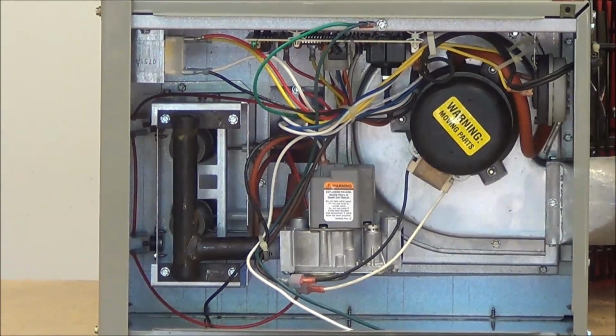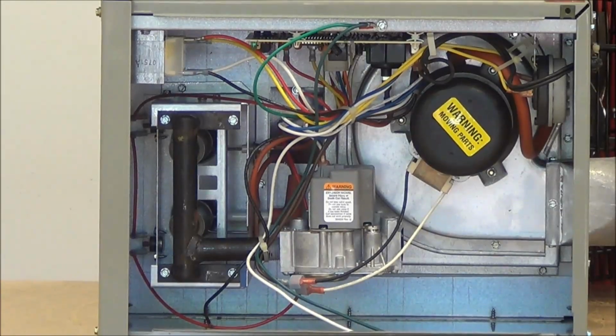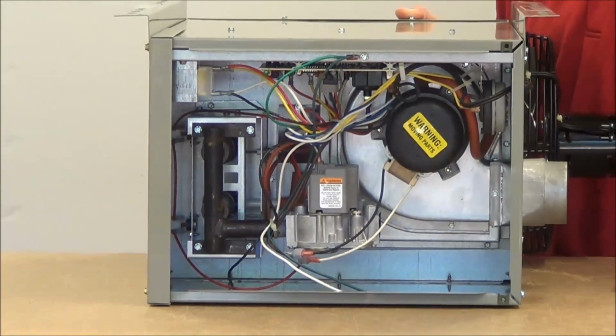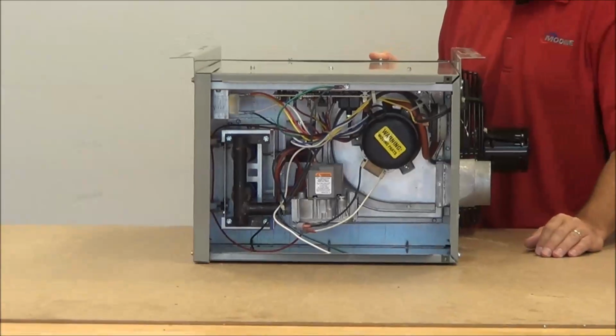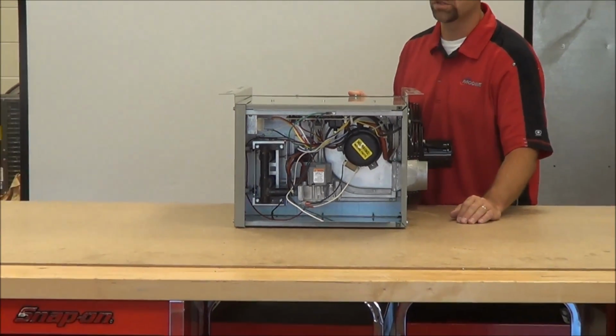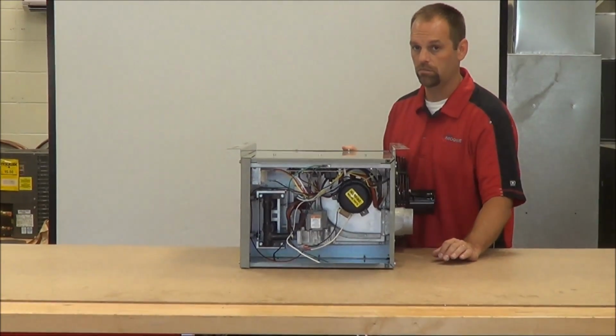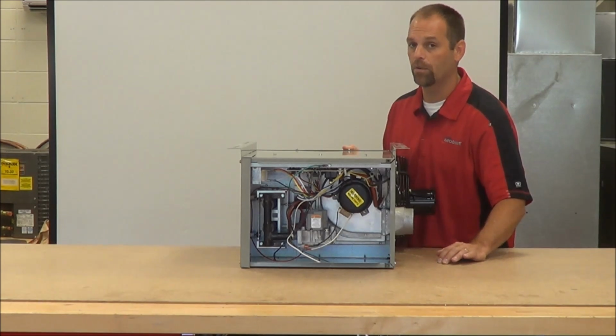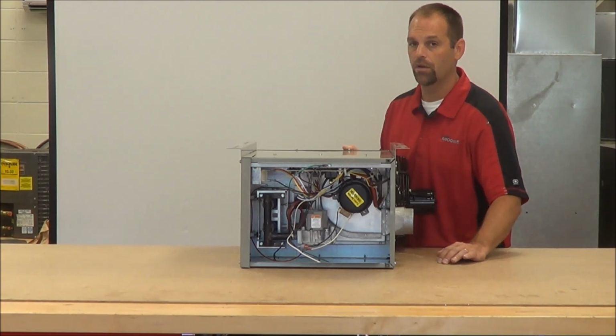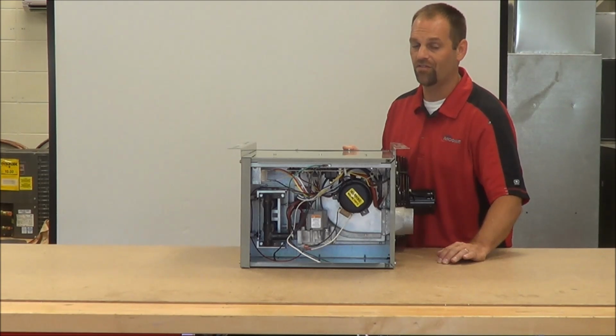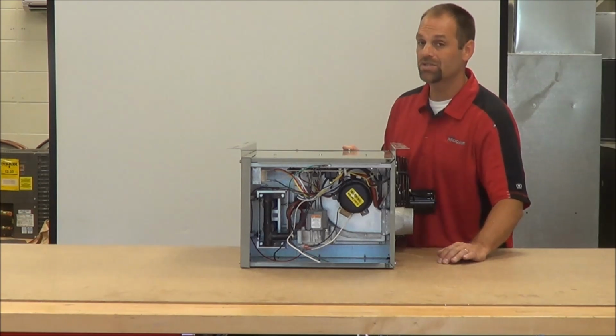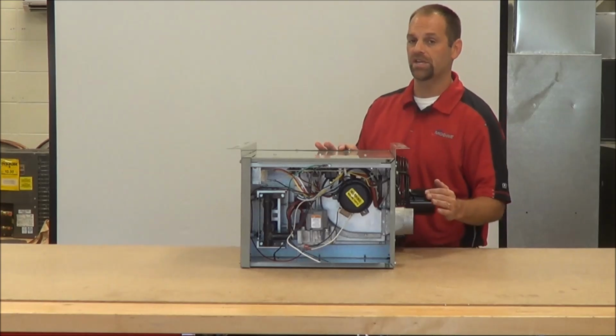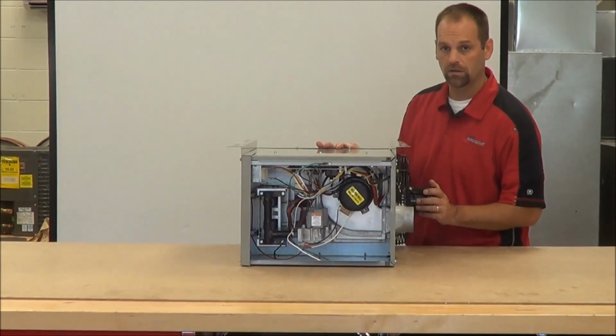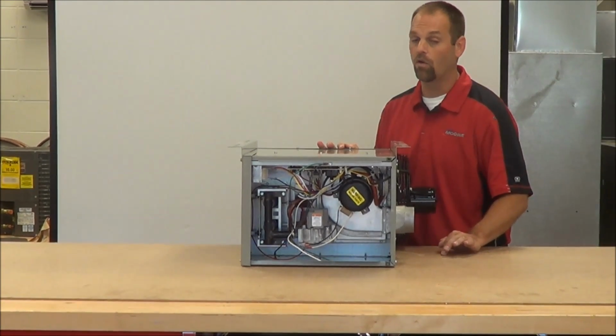If you're reading those readings correctly, you're going to want to check your secondary side, the low voltage side. On the low voltage side, you should read 24 volts. If you put your leads on that transformer and you're reading 0, okay, that secondary side has failed.